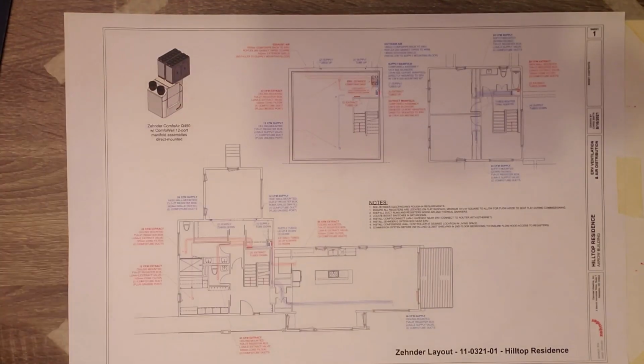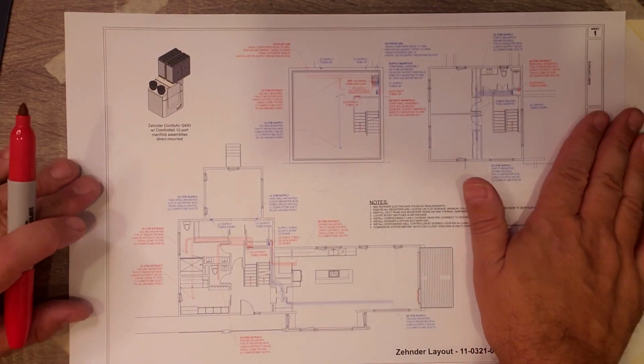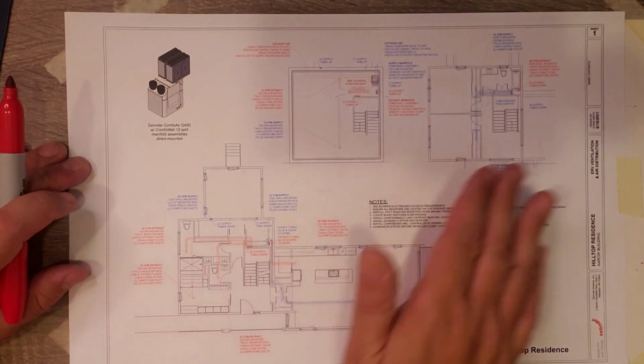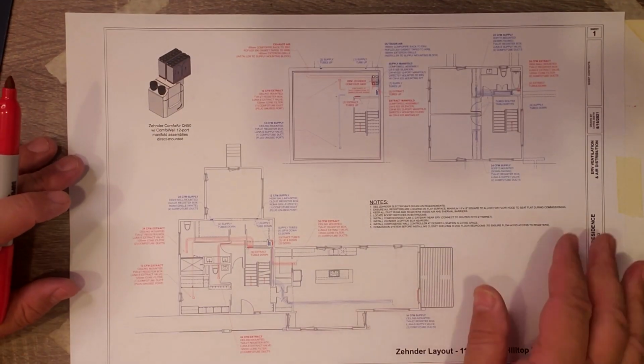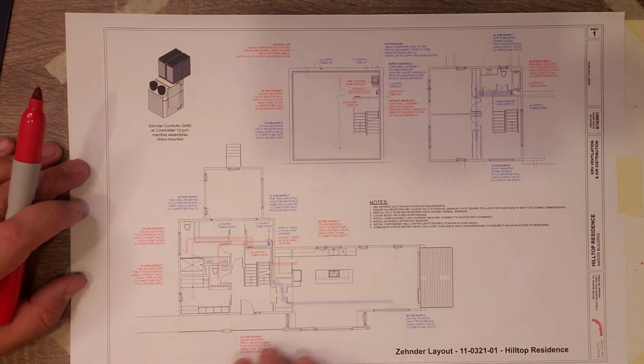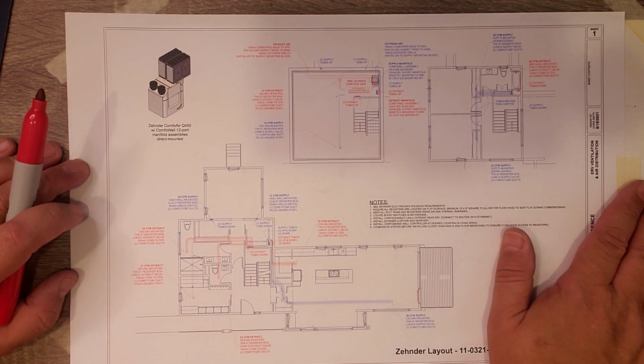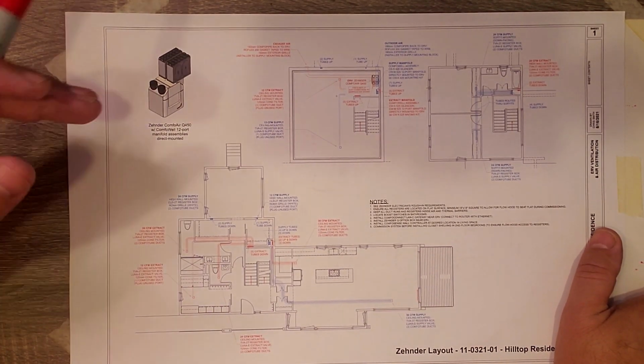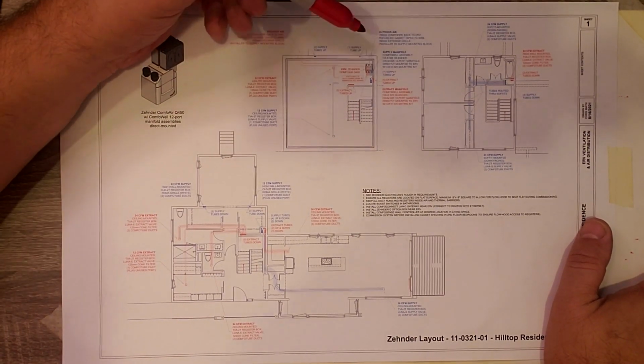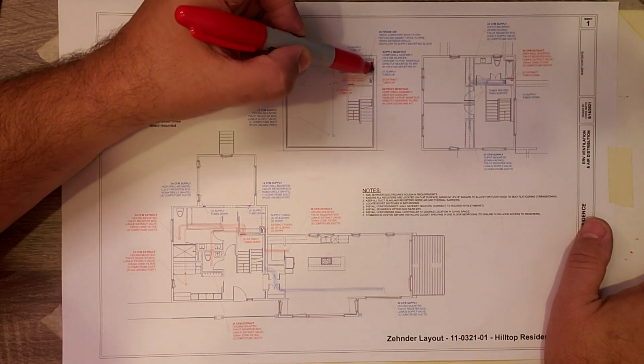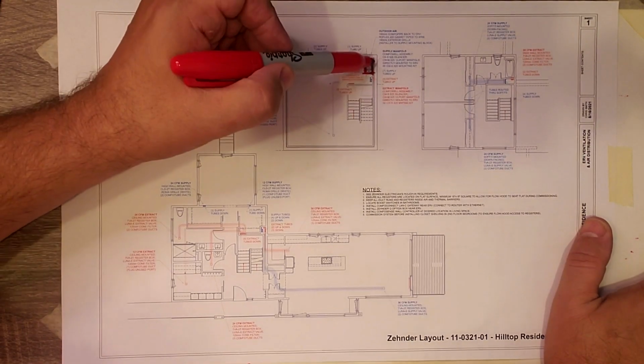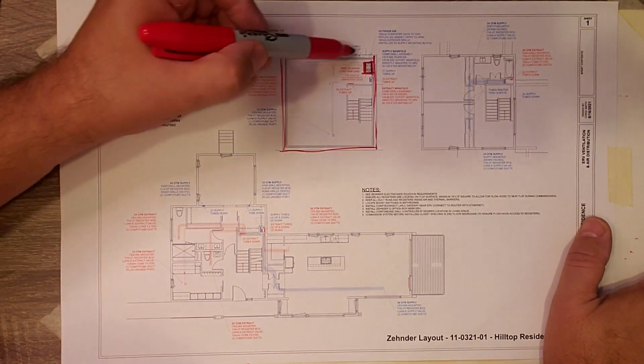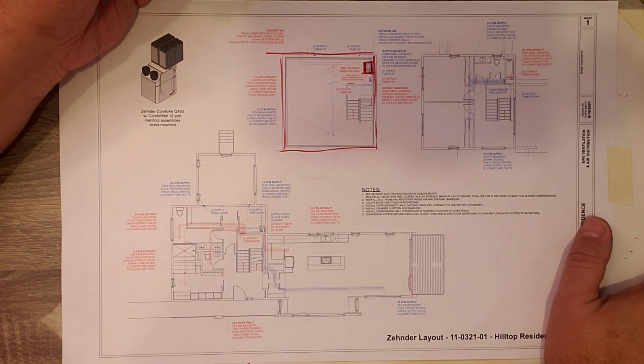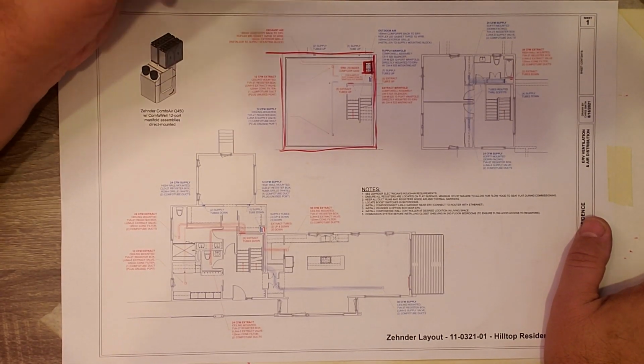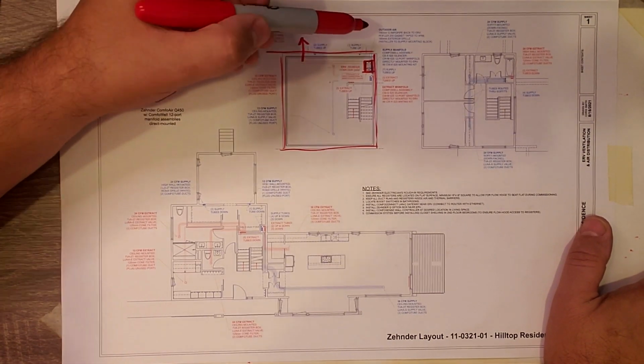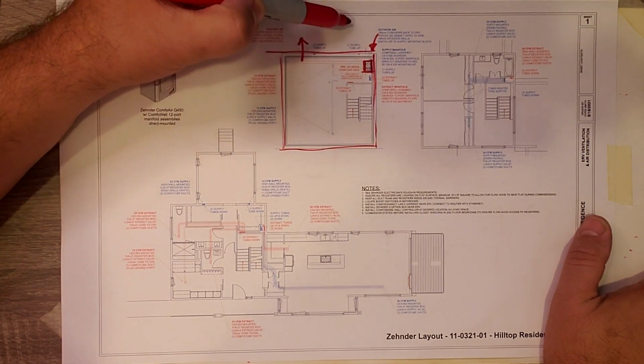Let's talk about this sheet. We send Zehnder a background on a plan, and Zehnder sends us a full layout of their system. First, let's look in the basement - for the video we're standing down here, we have the unit in the basement, this is the basement here. One of the things we talked about was the exhaust air and the supply air being a minimum of 10 feet apart.